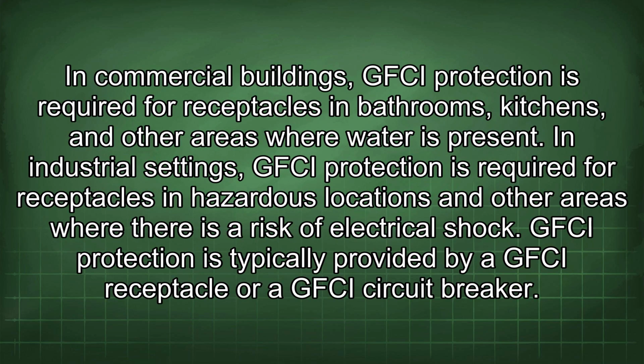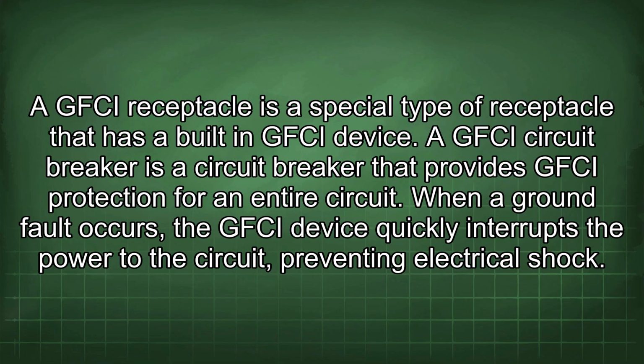In commercial buildings, GFCI protection is required for receptacles in bathrooms, kitchens, and other areas where water is present. In industrial settings, GFCI protection is required for receptacles in hazardous locations and other areas where there is a risk of electrical shock. GFCI protection is typically provided by a GFCI receptacle or a GFCI circuit breaker. A GFCI receptacle is a special type of receptacle that has a built-in GFCI device. A GFCI circuit breaker is a circuit breaker that provides GFCI protection for an entire circuit.